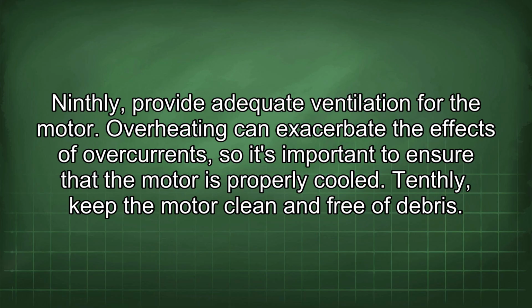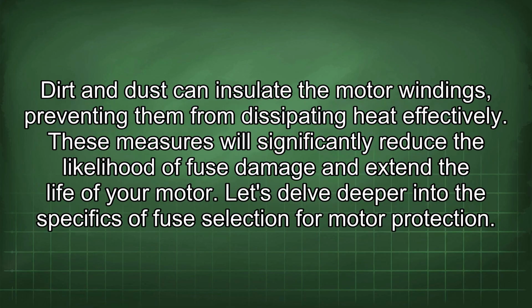Ninthly, provide adequate ventilation for the motor. Overheating can exacerbate the effects of overcurrents, so it's important to ensure that the motor is properly cooled. Tenthly, keep the motor clean and free of debris. Dirt and dust can insulate the motor windings, preventing them from dissipating heat effectively. These measures will significantly reduce the likelihood of fuse damage and extend the life of your motor.